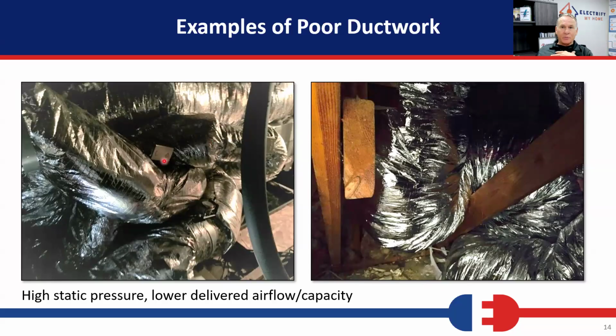But when we do it on a system like this with a bunch of trunk lines, we're already squeezing the air into a bunch of small spaces. And then we're going to shut off these dampers in little areas. So a better way to do this would be to put two maybe 16-inch dampers feeding into a pressure plenum that has the other ductwork coming off, or a graduated Y branch duct system, so that the air can smoothly move through there and we don't have all that resistance at the beginning. If you think about it, if I've got one 16-inch start collar, I have one place where there's a 35-foot reduction. If I've got a bunch of home runs coming off of that plenum, each one of those has 35 feet of length before it ever gets out of the plenum and into the duct.